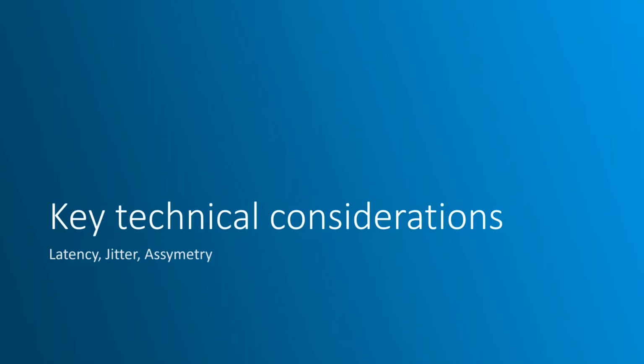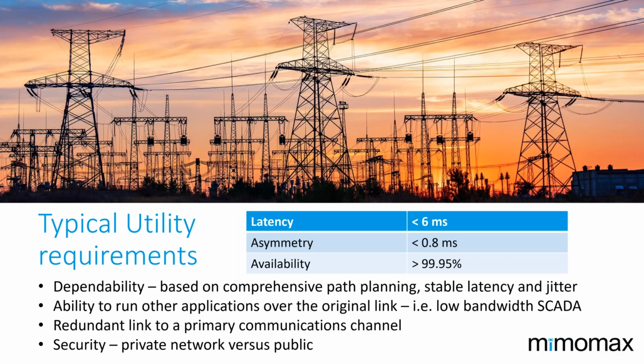Some of the key technical considerations for teleprotection really come from three main requirements, probably four if we consider jitter: latency - the requirement for category 1 latency is sub 6 milliseconds, certainly less than a cycle time - and asymmetry is another, we'll talk a little about that. I think the standard typically says 2 milliseconds, but we're seeing requirements less than 1 millisecond or 0.8. I think the MIMO technology sits around 0.4, depending on the equipment and interfaces you're using.